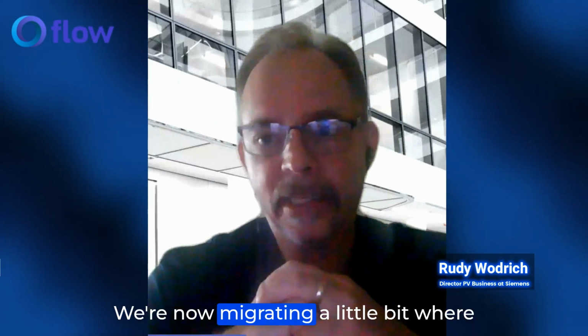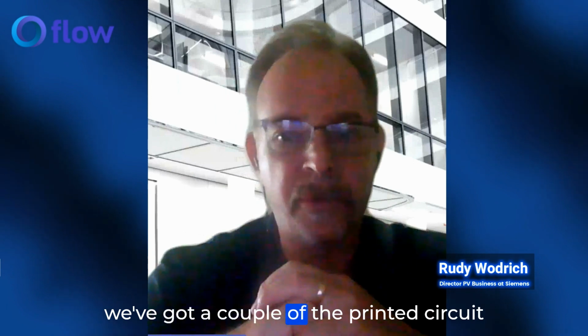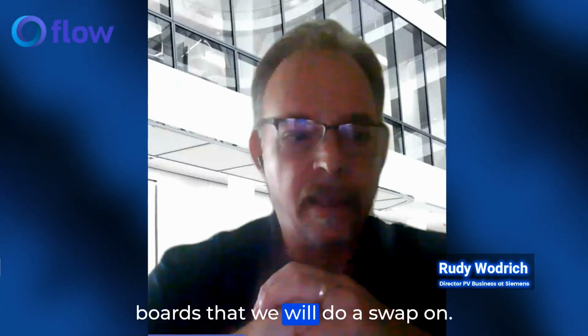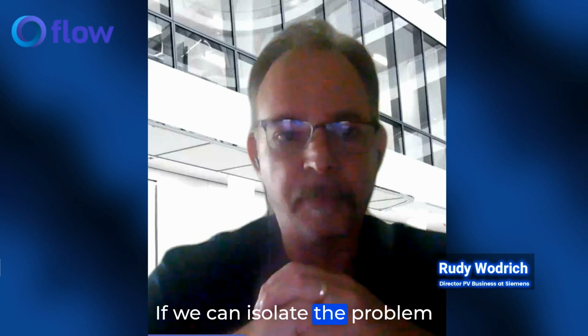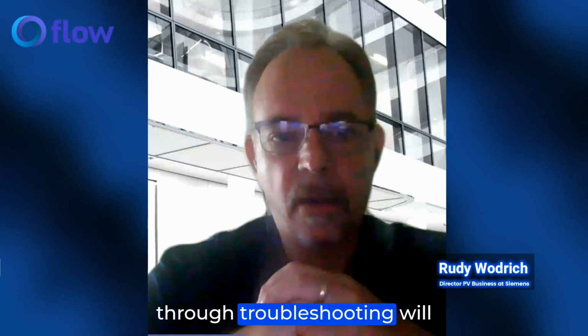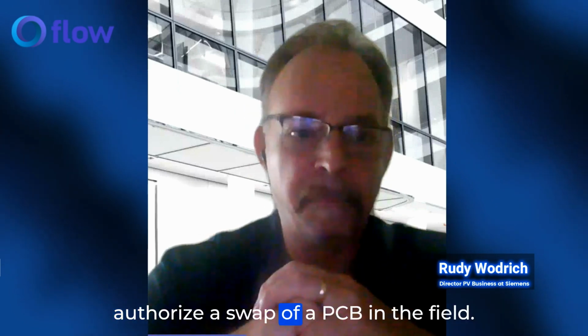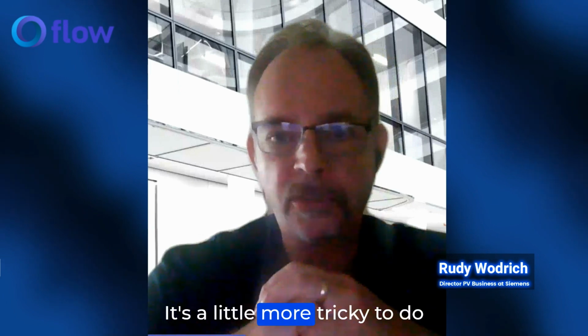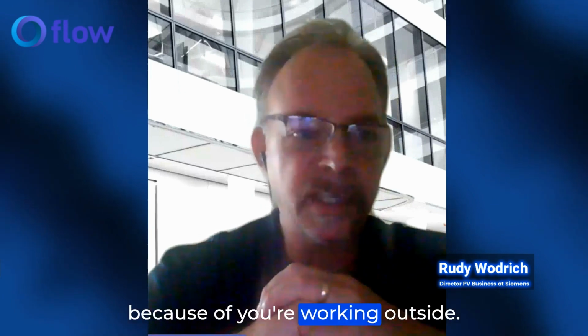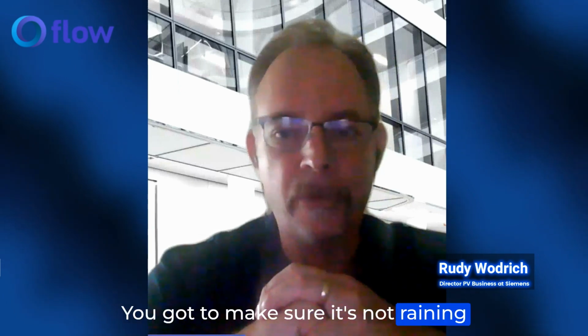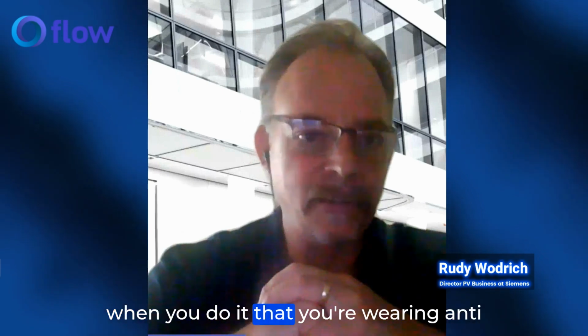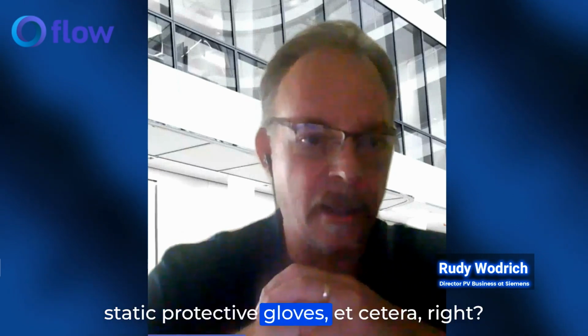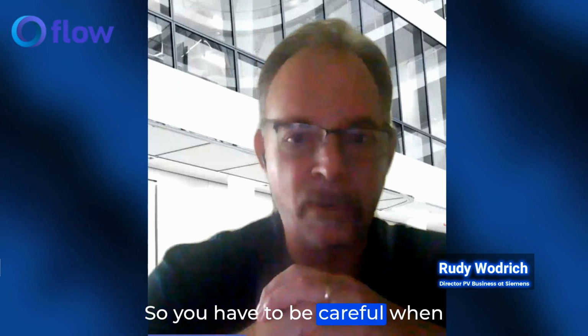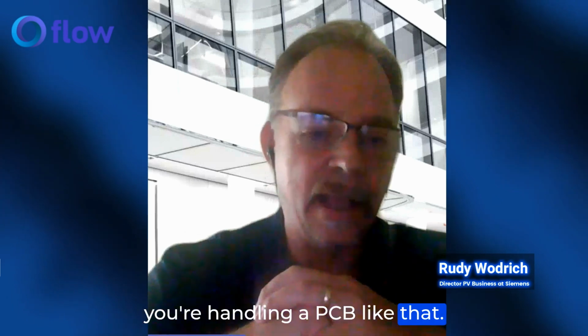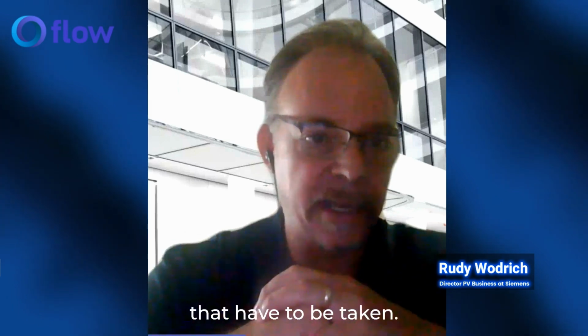We're now migrating a bit where we've got a couple of printed circuit boards that we will swap. If we can isolate the problem through troubleshooting, we'll authorize a swap of a PCB in the field. It's a little more tricky because you're working outside—you have to make sure it's not raining, that you're wearing anti-static protective gloves, etc. So there's some extra precautions that have to be taken.